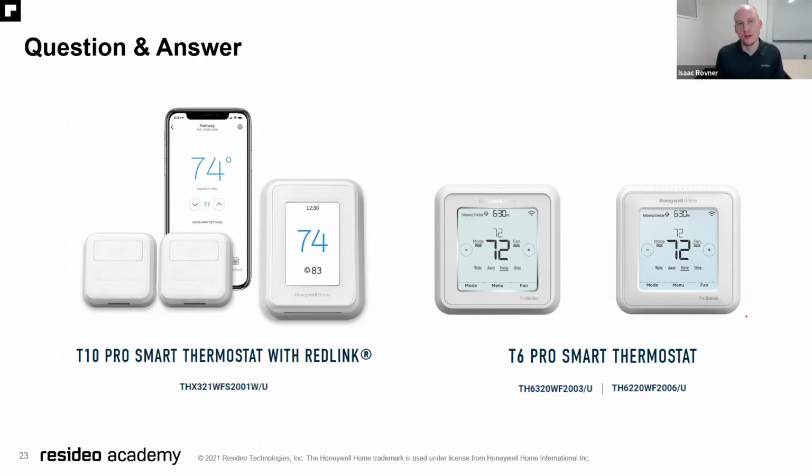Yeah, I know at least one. I believe the droop is set to comfort. So a lot of those things are set by default to comfort. If you want to actually adjust the specific droop setting, you can certainly do so within the installer setup. Yeah, and to that point, the timer settings, I believe, are defaulted to off. So if you want to upstage time in addition to droop, you have to select something.